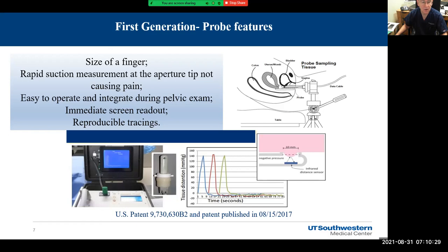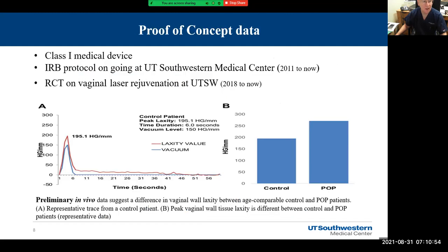Then on the left of that cartoon, you'll see deflection curves. And here you'll see 3 in a row displayed in real time on the screen shown on the left. So several measurements can be obtained consecutively. The process is rapid to execute, not painful, and can be easily integrated during a routine pelvic examination. This is a class 1 medical device, basically a device that is used for measurement like a thermometer.